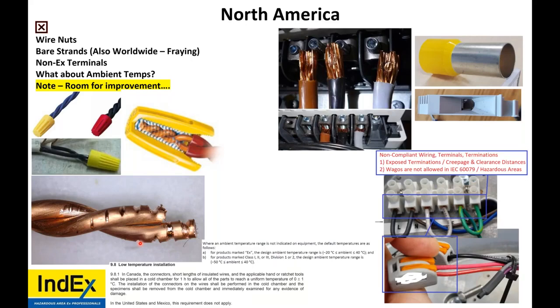Now, in the American one, where ambient temperature range is not marked, where it says EX, it has to be rated from -20 to 40 degrees. Well, these ones on the bottom right, the wire nuts, not EX rated. And if the product's marked for class 1, class 2, or class 3, division 1 or 2, well, once again, they're not rated for that. And it says the ambient temperature range of -50 to 40 degrees Celsius. So once again, they're really not good for most installations. And they're not marked for hazardous areas. So why are they used? There's room for improvement, let's put it that way.